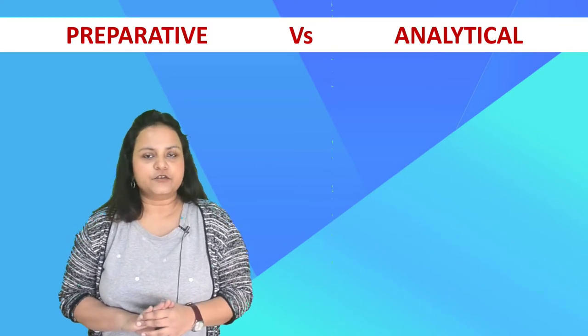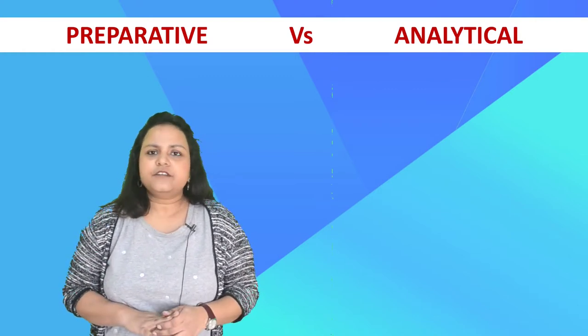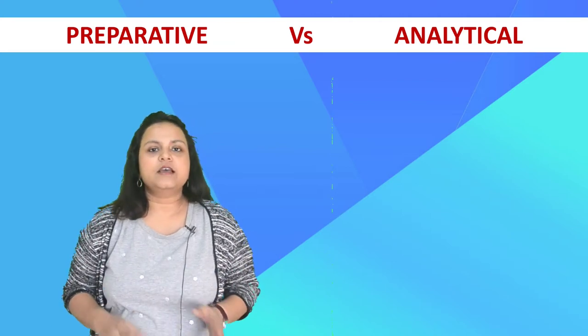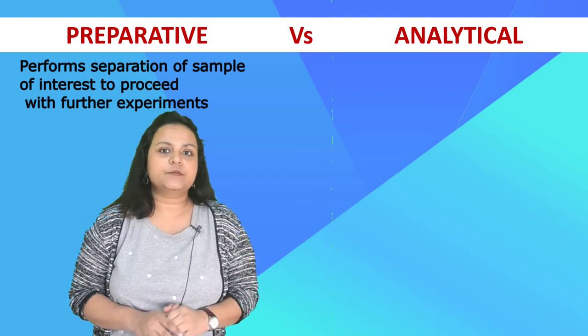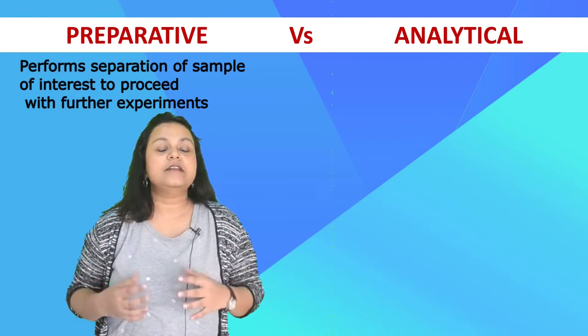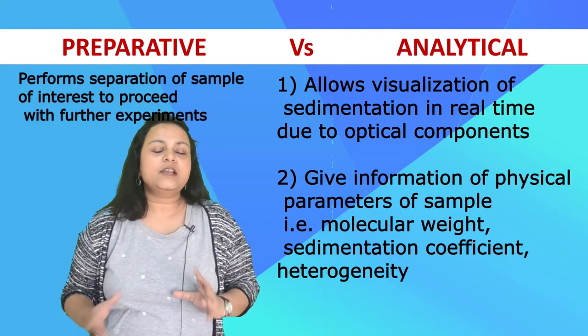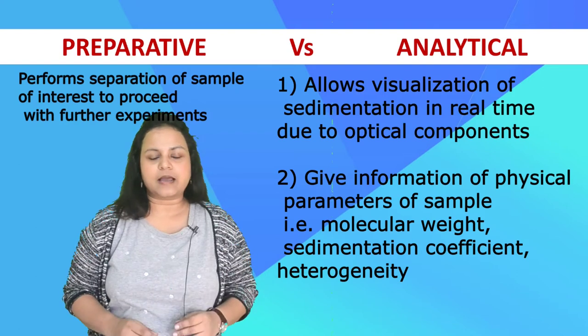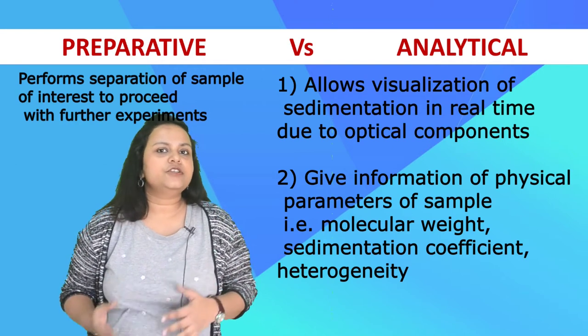Based on these properties, there are five kinds of centrifuges we will be discussing today. The first four are preparative centrifuges and the last is a modification of the ultracentrifuge — the analytical ultracentrifuge. A preparative centrifuge is simply for the purpose of separation or sedimentation, but the analytical centrifuge allows you to observe this process in real time using optics installed in the centrifuge, giving you valuable information about molecular weight, sedimentation coefficient, and sample homogeneity.